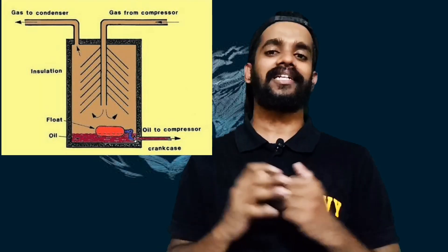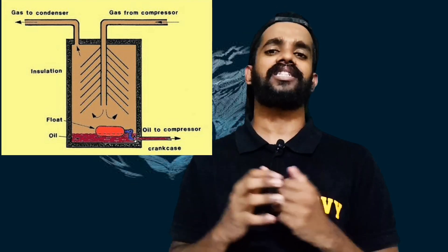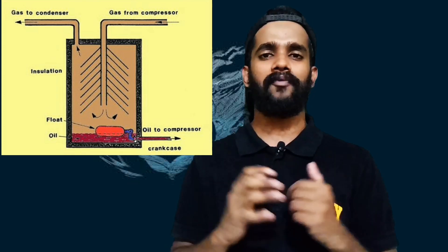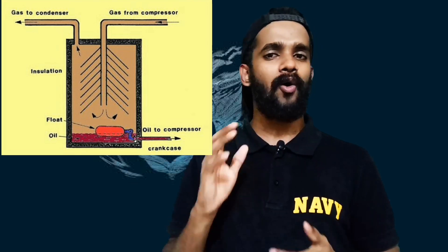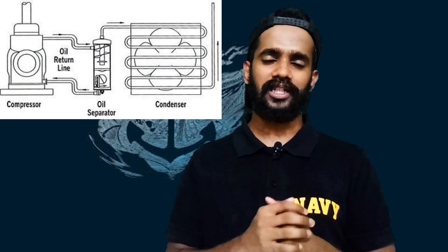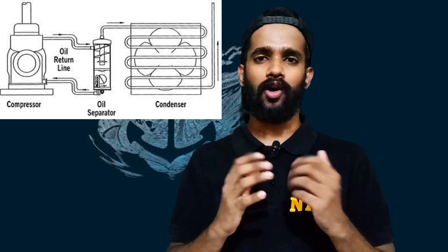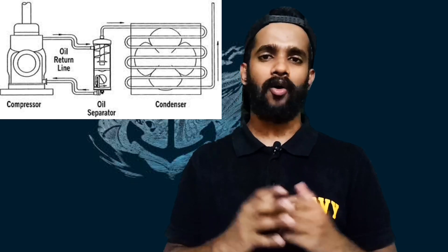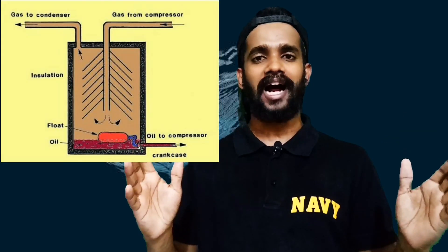You can now see a typical oil separator on screen. It is an impingement type of oil separator which has baffle plates. As you can see clearly from the diagram, it is a closed type of vessel with a series of baffles. The refrigerant entering the oil separator has high velocity because it has just been discharged from the compressor.